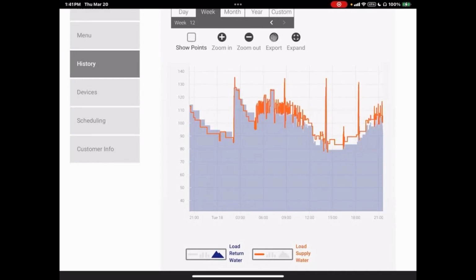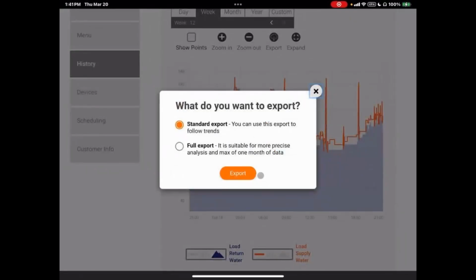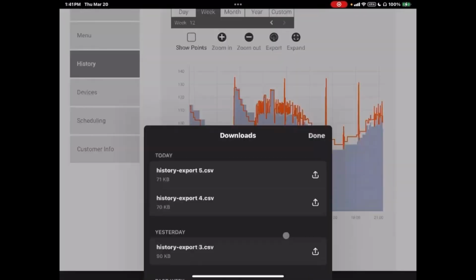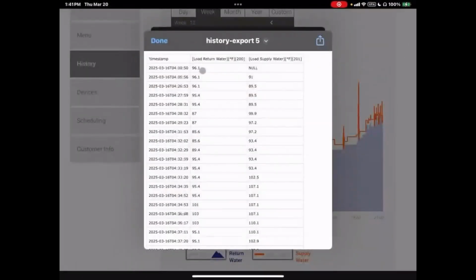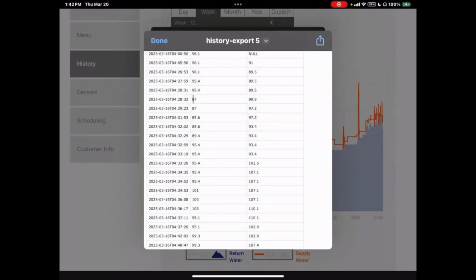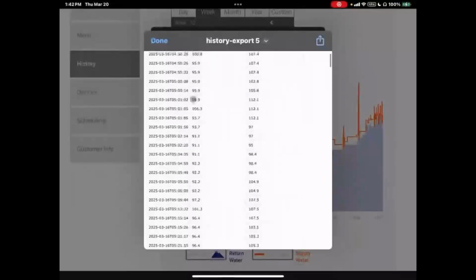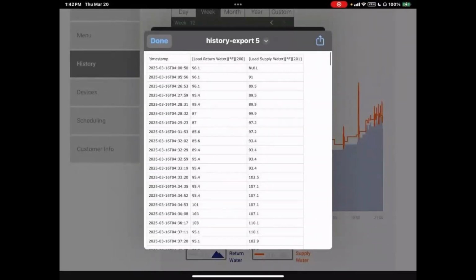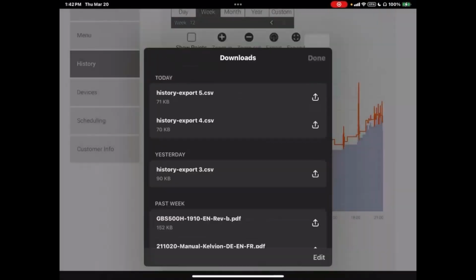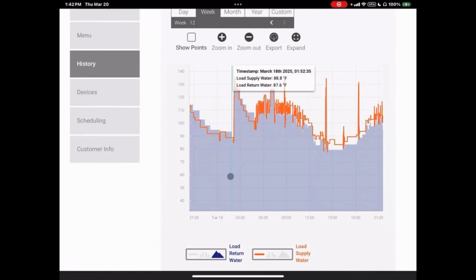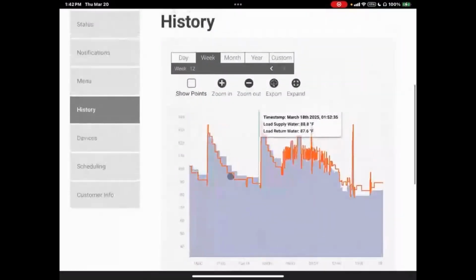And I can also come in here for the view selected and I can export this data. If I choose export here, it will download this information in a file, and it's going to show it kind of like I'm actually on an Apple device at the moment, but it's like an Excel spreadsheet. You can see here that we have return water temp and supply water temp, and basically this is updating about every 3 to 5 seconds. And so you can go down to the timestamp of the area that you're interested in. And again, you can have up to 10 columns on here, depending on which metrics you want to check out and look at. So this history tool here becomes incredibly useful if you want to see exactly what the heat pump is doing over a given time period.